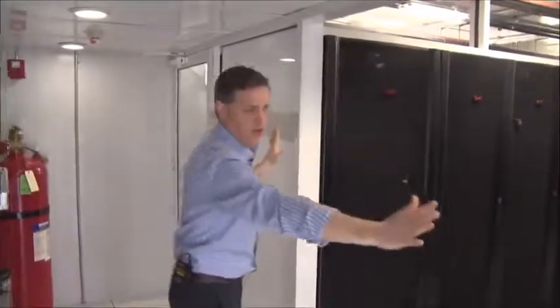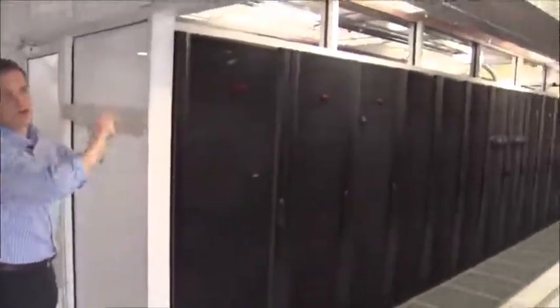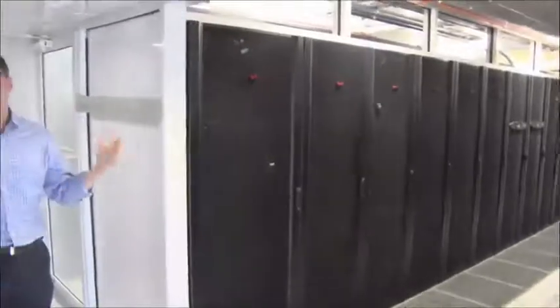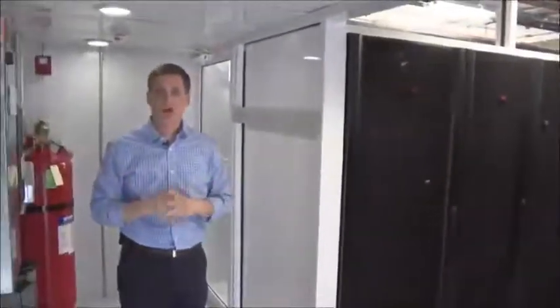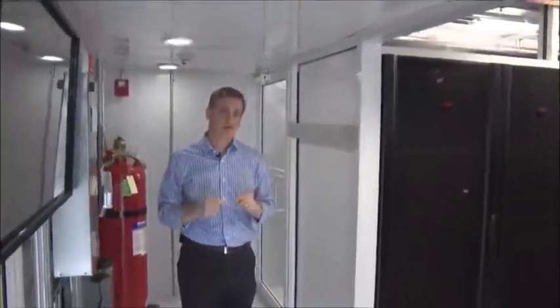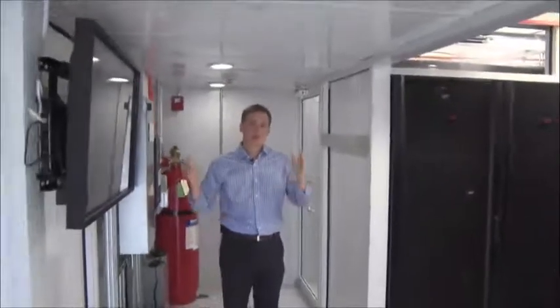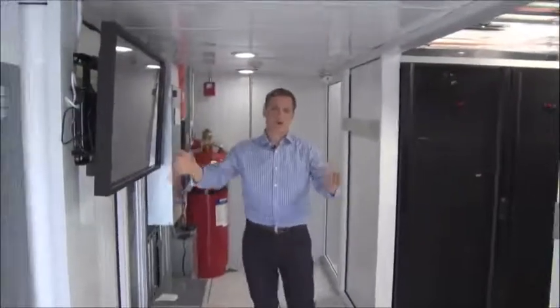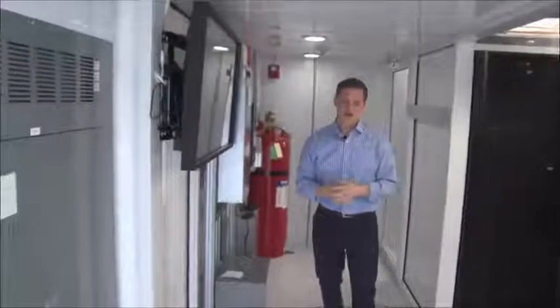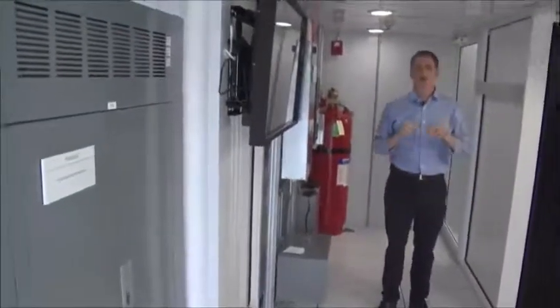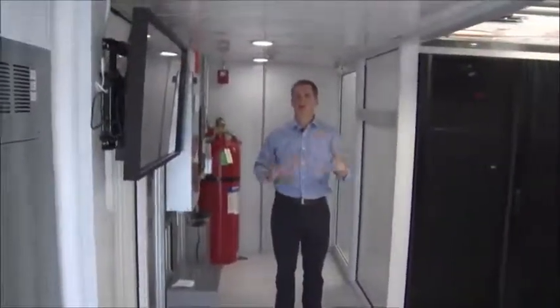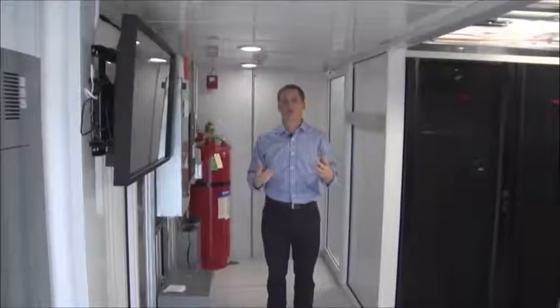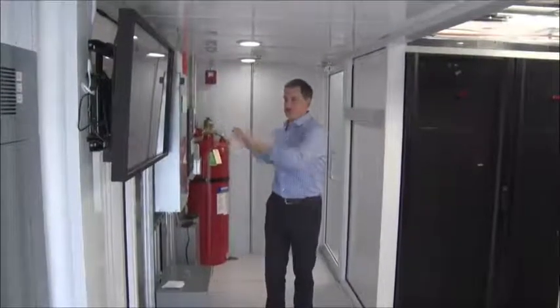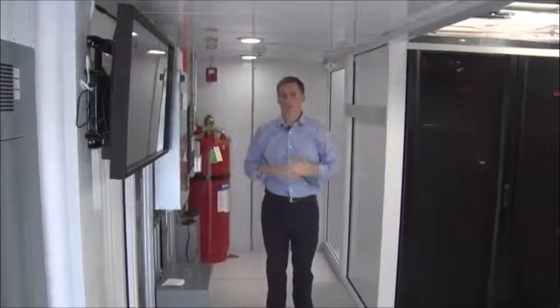We may have a door here. Again, this may be a preference where you want this area completely isolated - that can be done as well. So we have a lot of options in the lobby area. We can make this bigger, we can make this smaller. We do have to comply with codes and clearances, so we still have to have 40 inches of clearance if we have a 480 volt panel, for example. So there are some restrictions in terms of what we can fit. Again, that goes into the trade-offs we go through in the design process, making sure we can fit all the stuff in here.